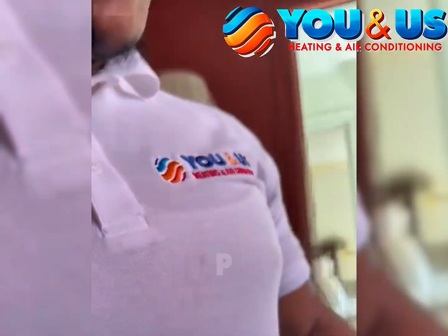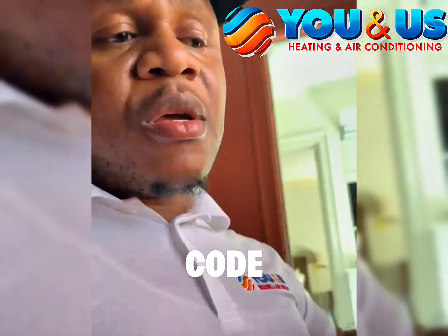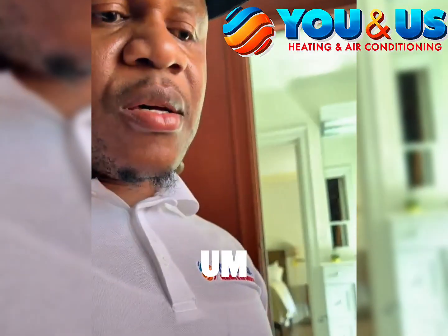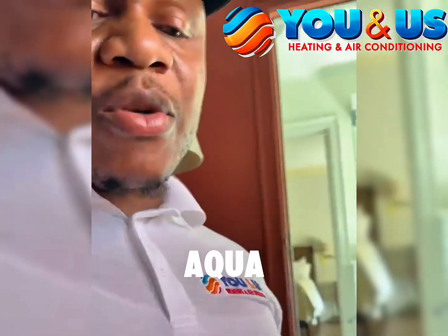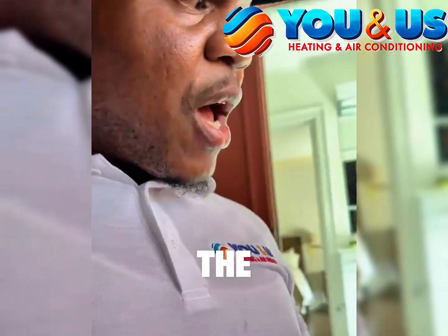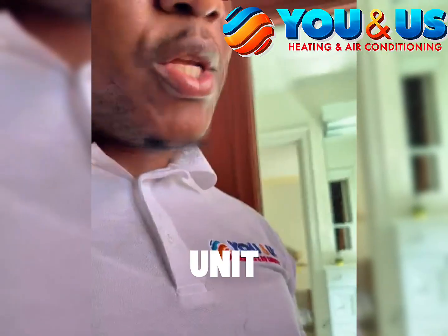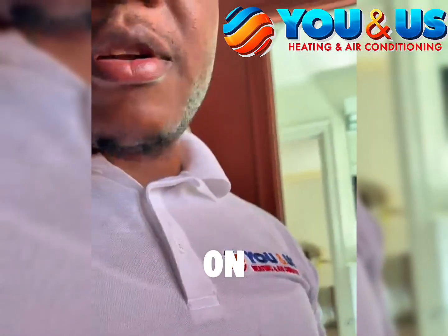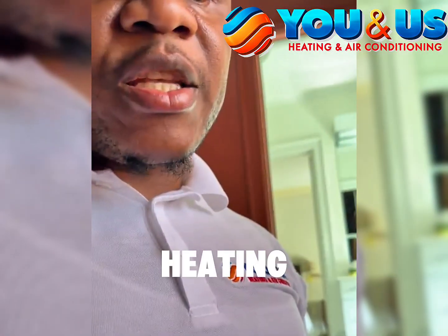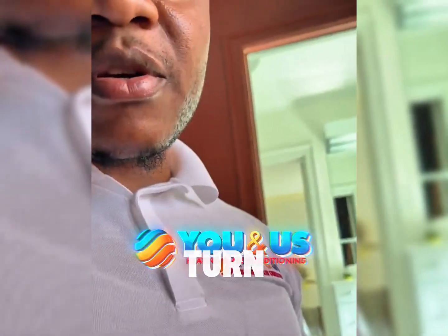So to fix a Daikin Applied PTAC unit error code number 9: number 9 is for the Aquastat, and the reason for that is because the Aquastat is open. The Aquastat, especially for a steam unit, is what turns on the fan when in heating mode. If the Aquastat is open, it's not going to turn the fan on. All right, so that's how you fix it.